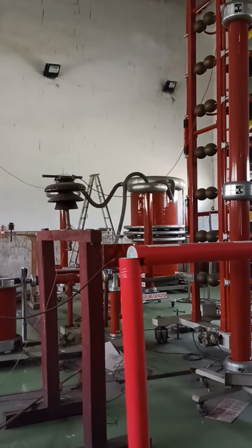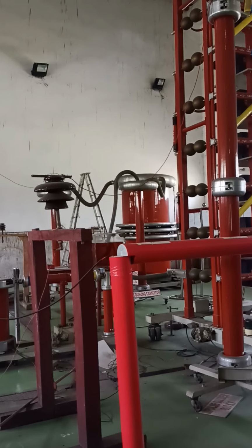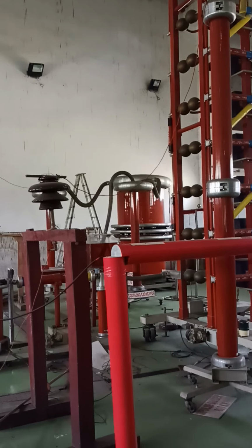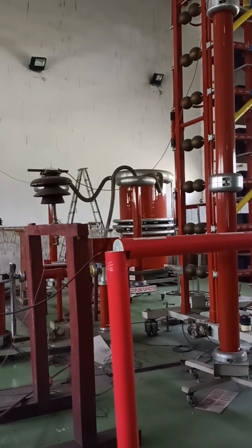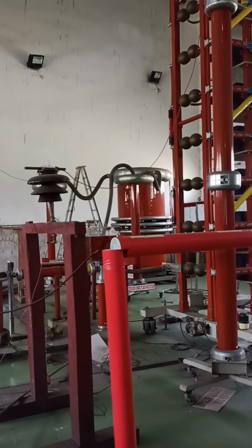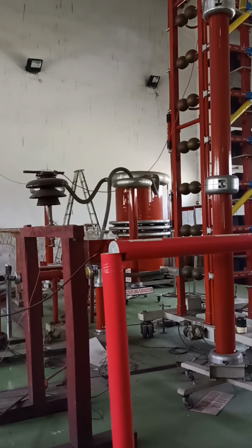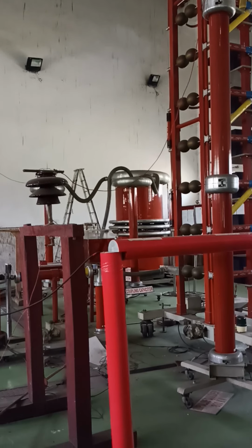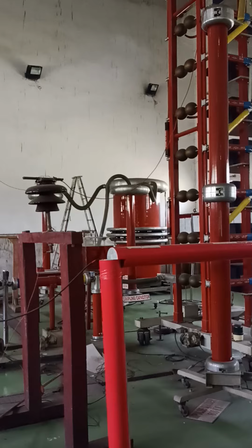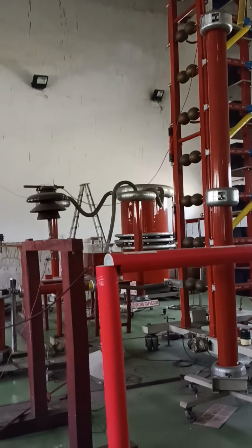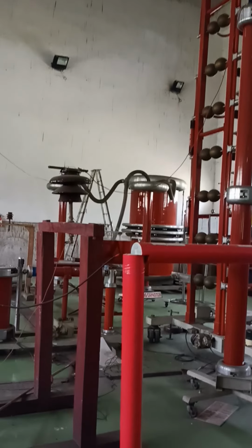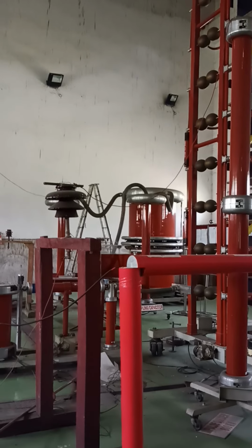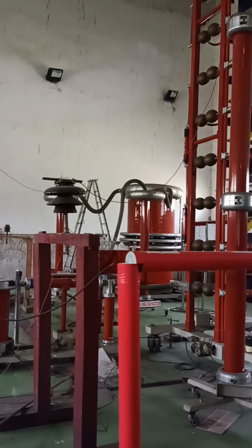Any insulator cannot block 100% current, so small microampere-level currents pass through those insulators. We detect those microamperes so that we can analyze the condition of the oil during normal operation. This is the partial discharge technique. We can analyze the health of any transformer and issue an early warning that the oil is getting degraded. We have to change it so that the whole system doesn't fail.